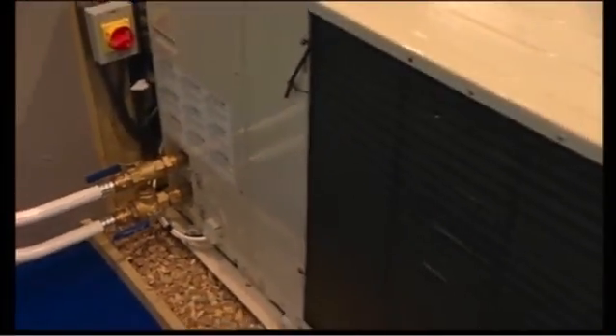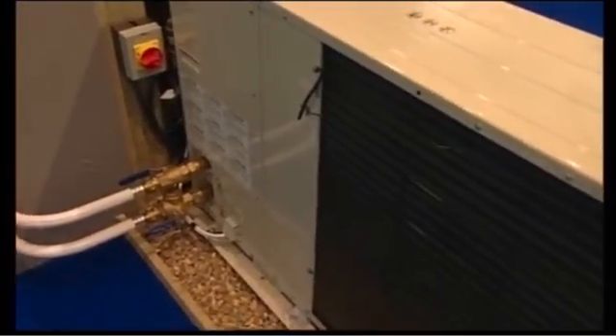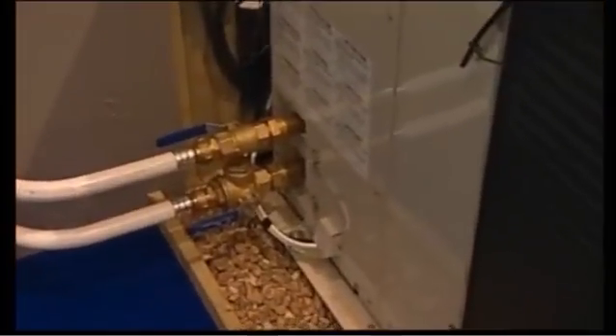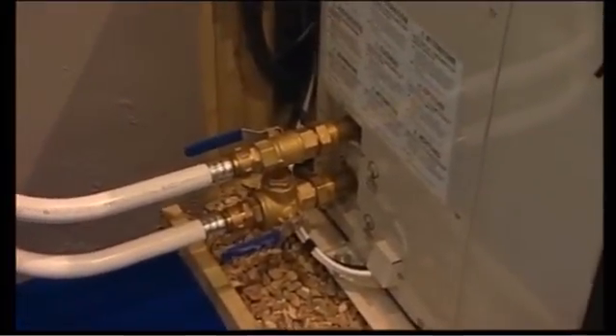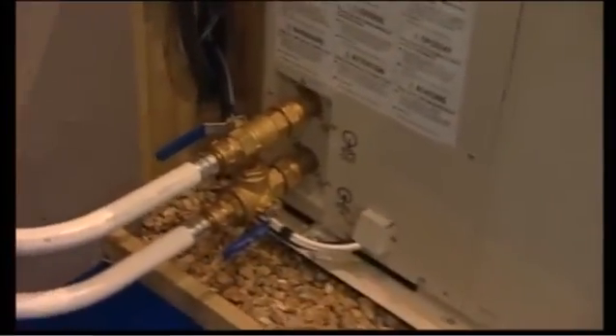Some people have told me these are three times more effective than boilers — is that really true? Yes, it can be. In the winter they're going to drop to around about 250% efficient, and some can be more — it depends on the ambient air temperatures. The new MCS-3005, which is an installer bible, says that throughout the year you must have a seasonal performance factor of around 300%, and that is the minimum guidelines.